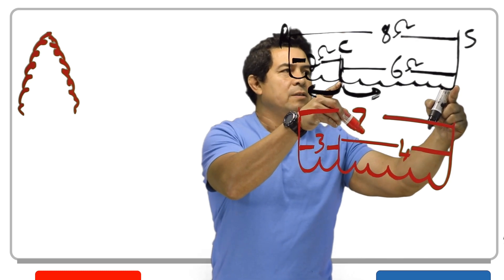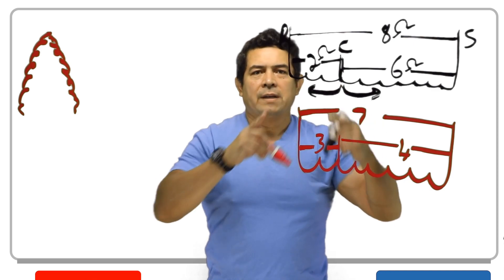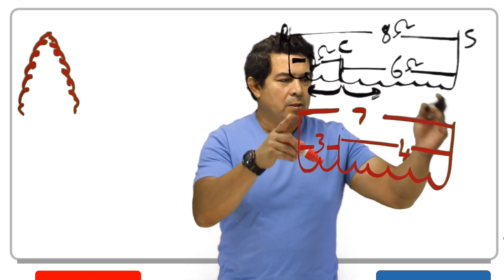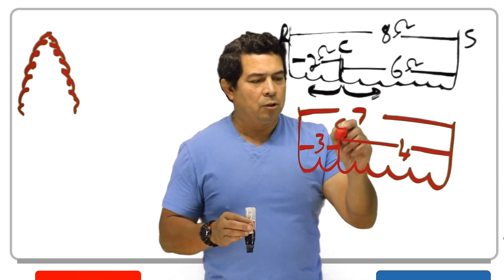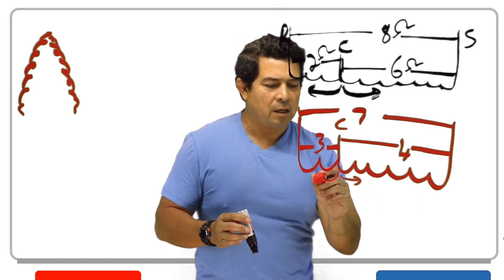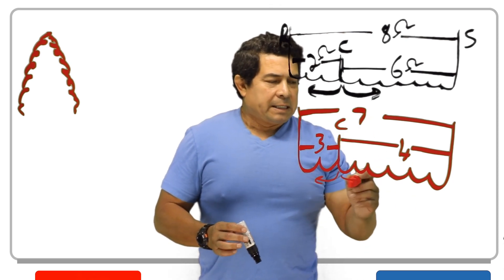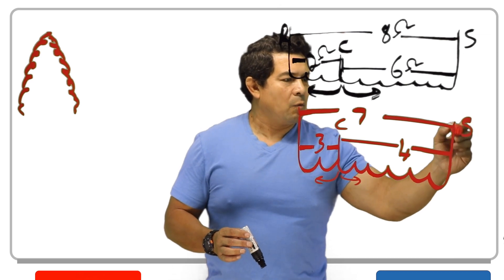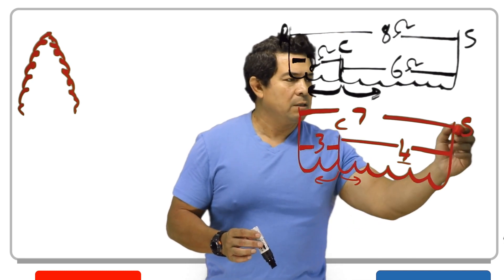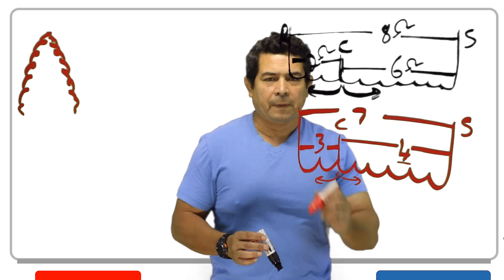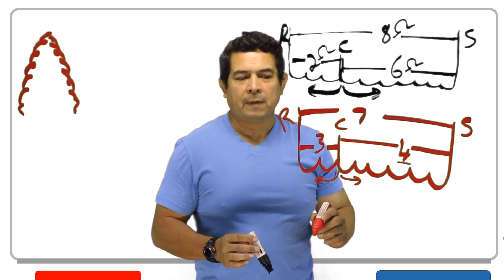The winding with the highest resistance is always your start winding. The one with the least resistance is going to be your run winding. So with our example of 7 ohms total, this middle connection is common to both. The side with 4 ohms has the highest resistance, so that would be my start winding, and the side with 3 ohms would be my run winding.